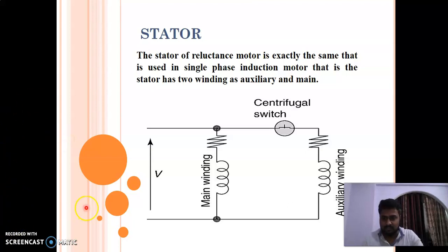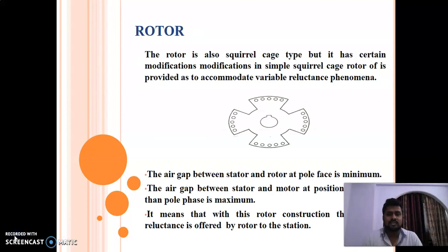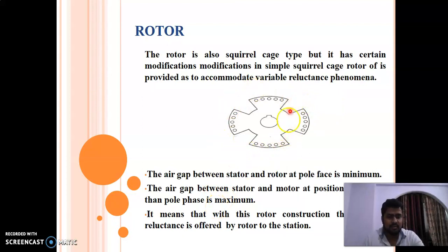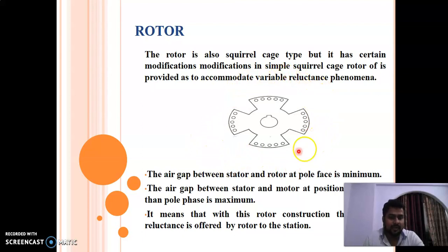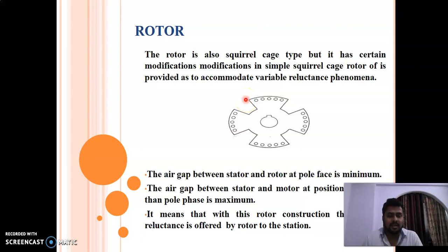Now let's come to the rotor part. The rotor is also a squirrel cage type, but there are certain modifications. These modifications have been done to the simple squirrel cage motor so as to accommodate the variable reluctance phenomena. The simple squirrel cage rotor has been modified to form a salient pole type construction. These salient poles facilitate the variable reluctance phenomena. Thick copper bars have been placed on all four rotor poles.